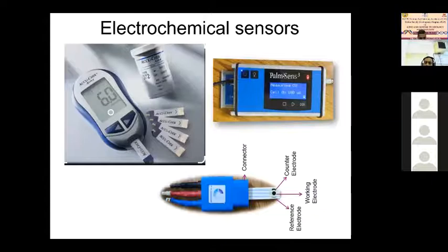And we do all our chemistry on this central dot. We immobilize our biomolecules here at the central dot, and that immobilization procedure requires a linking chemistry, which we do at our lab. In the case of the glucometer, glucose oxidase is immobilized on the membrane surface and interacts with the glucose to produce gluconic acid and then electrons.